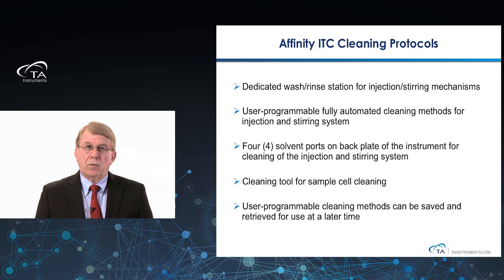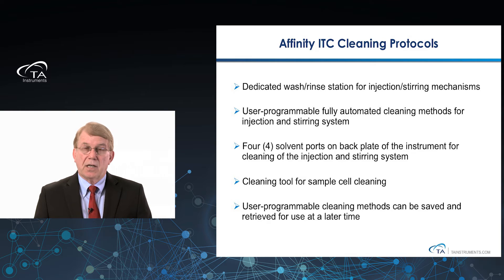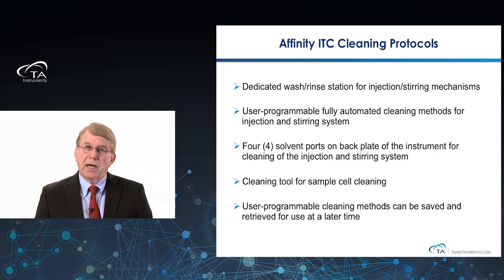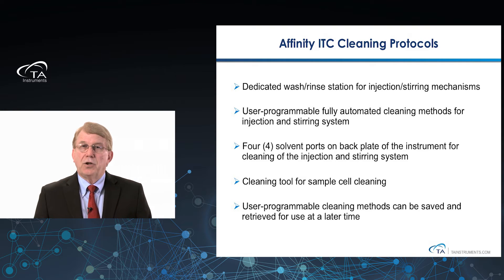One of the improvements on the Affinity ITC is a dedicated wash and rinse station for injection and stirring mechanisms. It is fully programmable by the user and you get fully automated cleaning of the injection and stirring system. On the stand-alone manual system, you still use a cleaning tool to clean the cell, but on the injection and stirring systems you have automated cleaning. You can choose from four solvent access points on the back of the instrument, so if you wanted to use methanol and water or a cleaning solution in a specific order, you can program it in and it will automatically clean the stirring and injection system. Cleaning methods can be saved and retrieved for later use.